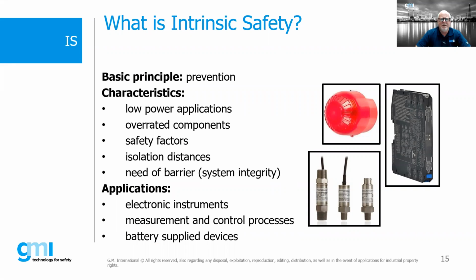So again, it is a prevention concept. So it is definitely a low power application. The components that we use on the inside of intrinsically safe barriers are overrated, meaning that they will fail safe in many cases. We also have to have safety factors built into them, either redundancy or based upon those minimum ignition energy curves. We want to keep way below those. There are also some requirements for distances. And of course, we do require the barrier to maintain our system integrity.